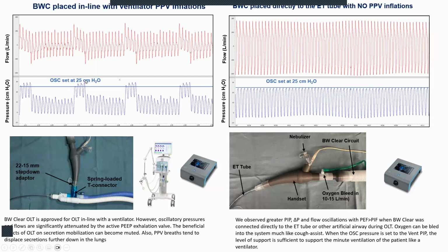But if we set that oscillatory pressure at 25, why is it only going to like 12? It's because the ventilator expiratory valve is controlling the pressure in the system so that it's preventing it from going above 5 or 6 or whatever you set as your PEEP. So it's going to the atmosphere, and you're not getting those therapeutic benefits. And so most of them are approved in line with the ventilator, and they still will work. But you just need to keep in mind that the active PEEP exhalation valves are going to attenuate this.